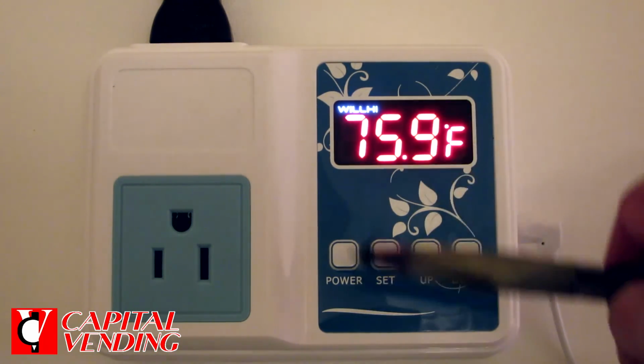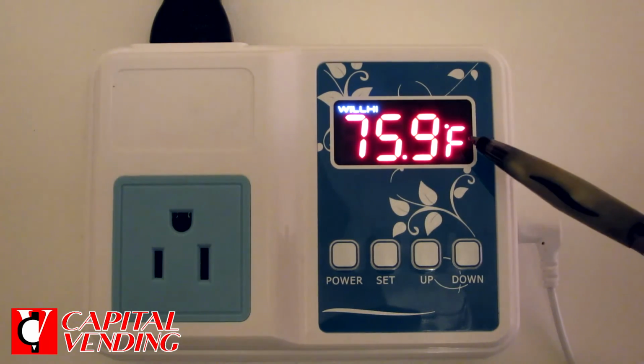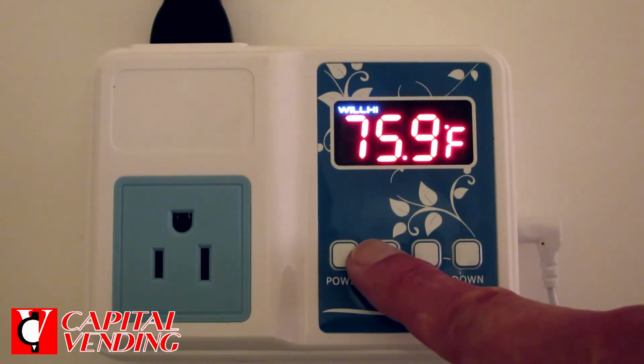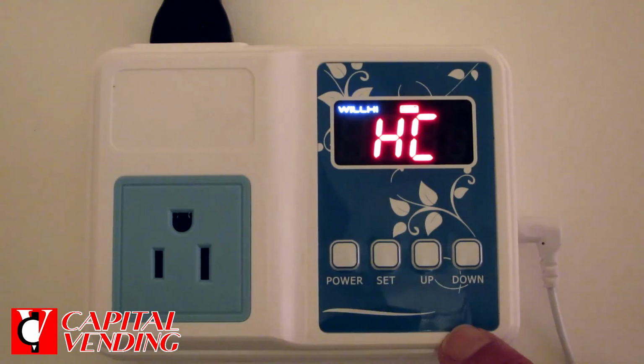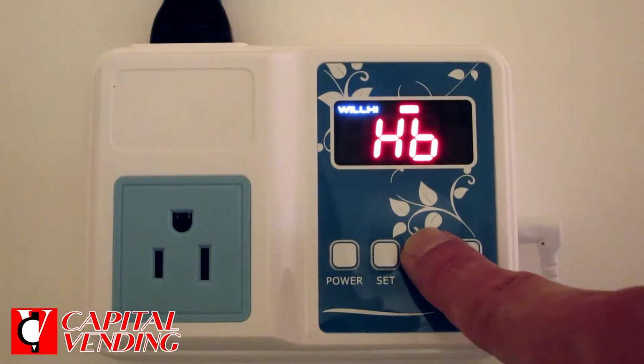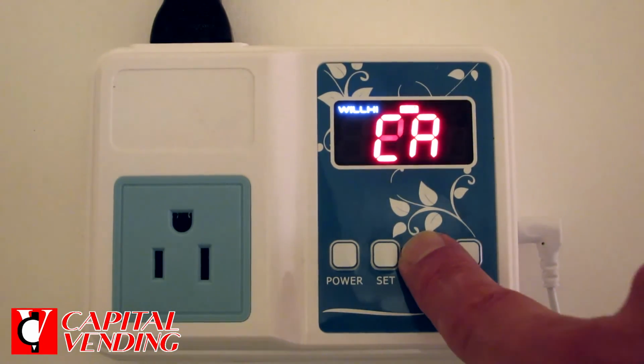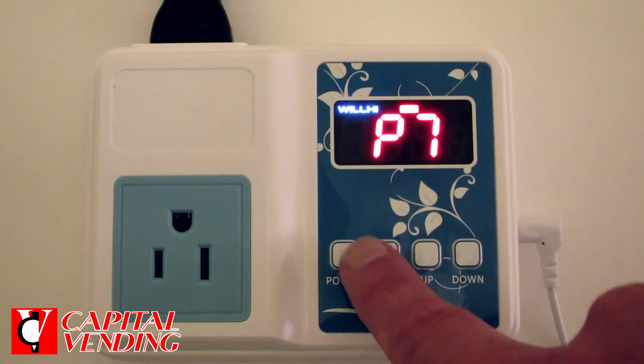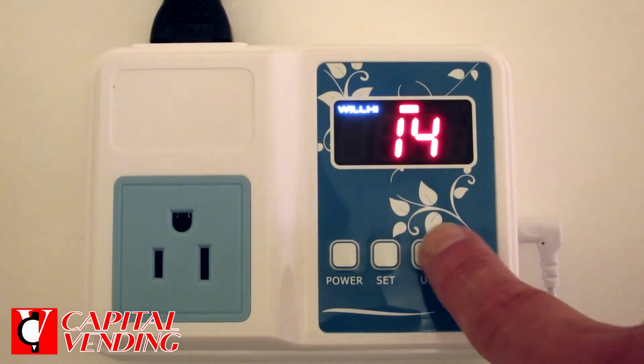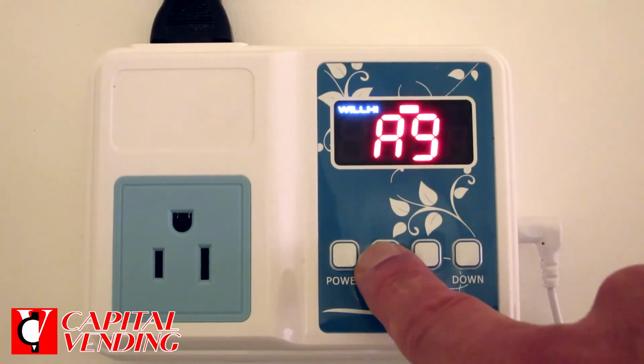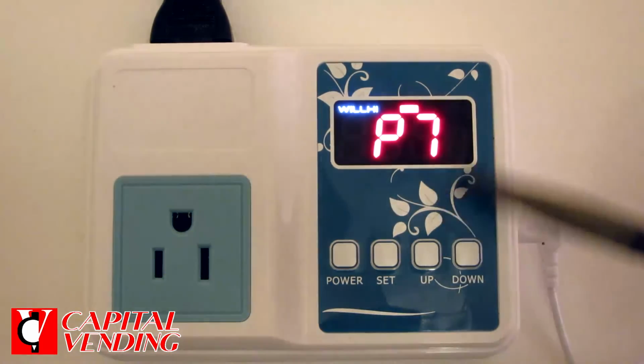So if you're programming it and it goes back to the ambient temperature, all you do is press set. Now we press up, scroll through the menu, skip CA. This P7 again is where we set my 15 minutes - you can increase or lower that, then put it back here.